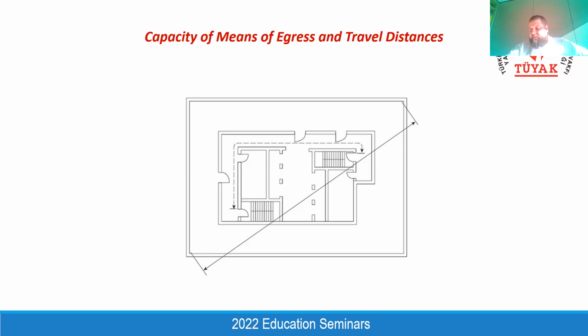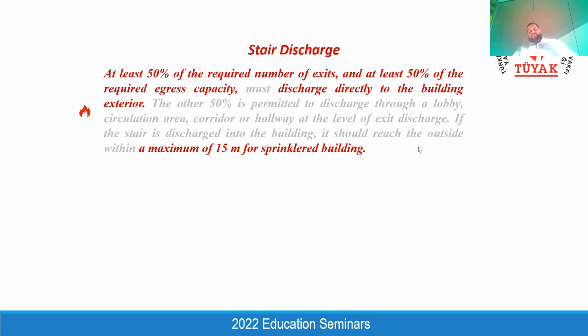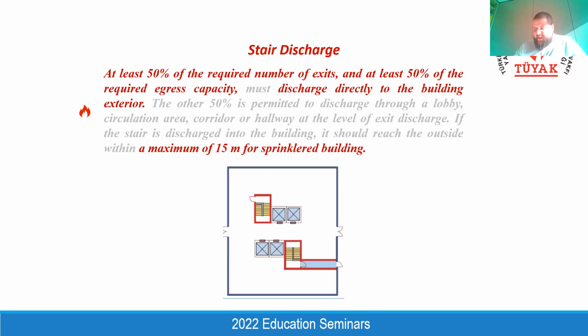All of the designers, all of the architects for today's construction work are trying to make these building cores as small as possible. That's why having a sprinkler system gives you a chance to design smaller corridors and also a smaller building core, and it will have a positive effect on the efficiency of your building design. That's why we always prefer to have a sprinkler system and take its advantages on the remoteness criteria. Also, as we talked about before during the architectural lesson, half of the staircases shall discharge directly to the outside of the building, and the other half is allowed to discharge on the lobby or the ground floor.